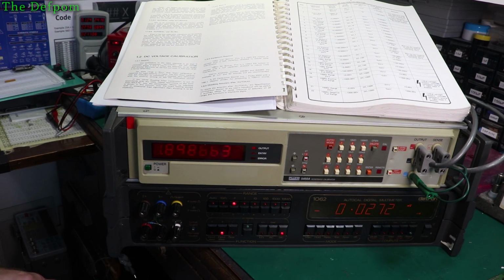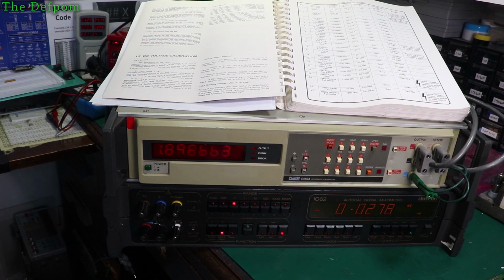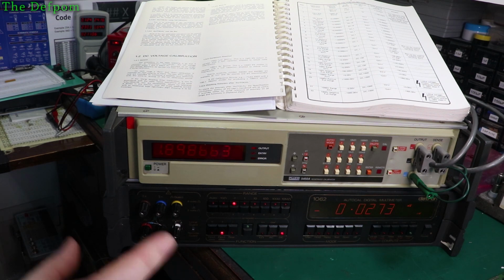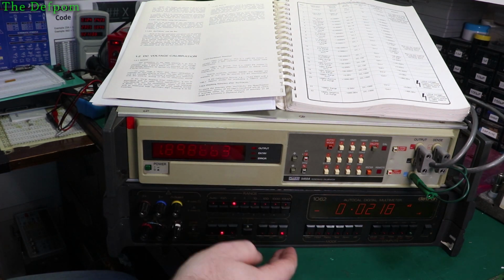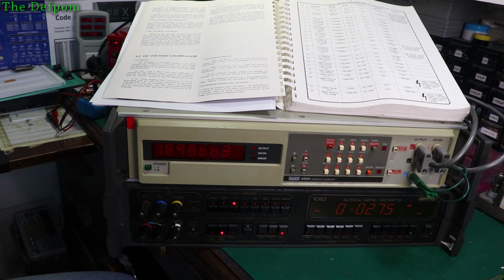What to do? What I've decided to do is go back to the DC volts calibration side of it and verify this and actually redo this part, because the linearity being off on the ohms means the DC linearity may also be off. I've already done this calibration once, but I thought, well, I'll do it again. I realised that the capacitor I had before was not the right capacitor. It's a 10 nanofarad, and the DC says a 1 nanofarad. I thought, hold on, that's not right. So I've got a 1 nanofarad across here now, and that's a 1 mega ohm resistor.